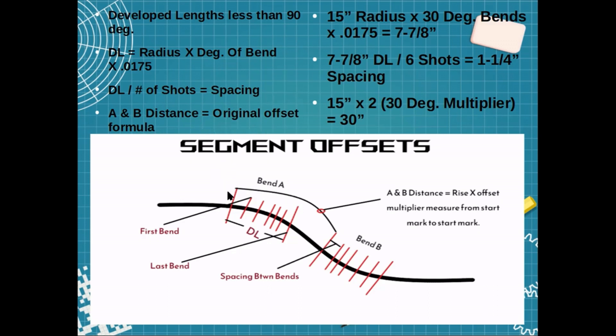The spacing — the A and B distance — is going to be 30 inches. You measure that 30 inches from the start mark of Bend A all the way to the start mark of Bend B. So from the start of Bend A to the start of Bend B should be 30 inches. From the start mark you'll begin laying out your segment bend for Bend A, and do the same for Bend B.